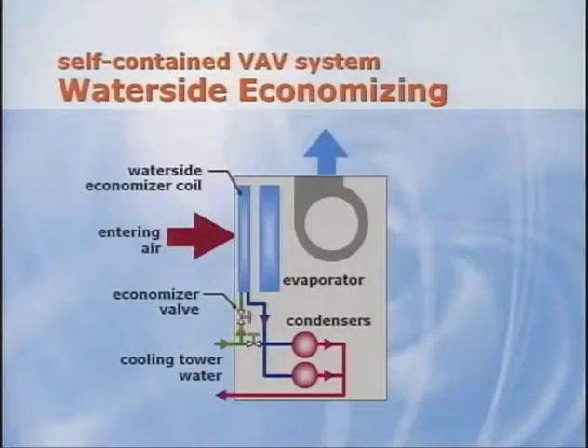As we mentioned, these self-contained units are typically not equipped with air-side economizers. They are usually installed in small mechanical rooms that are located in the core area of each floor of the building. Ventilation air is ducted down a vertical shaft to each floor, but that duct is usually sized for only the minimum ventilation requirement, not full economizing airflow. But this type of equipment can include a water-side economizer coil. When the weather and heat rejection load are such that the cooling tower is able to make cooler water, a valve diverts this cool water through the economizer coil that's located upstream of the evaporator.